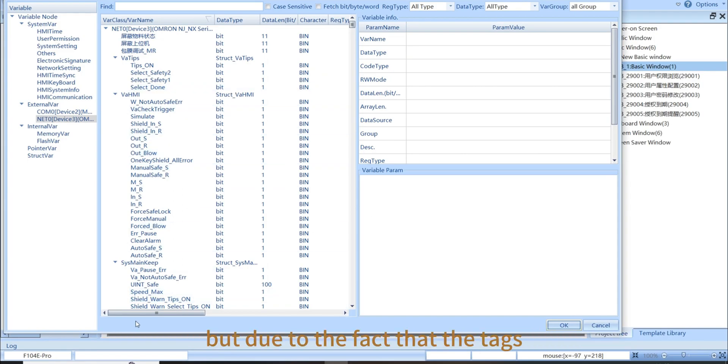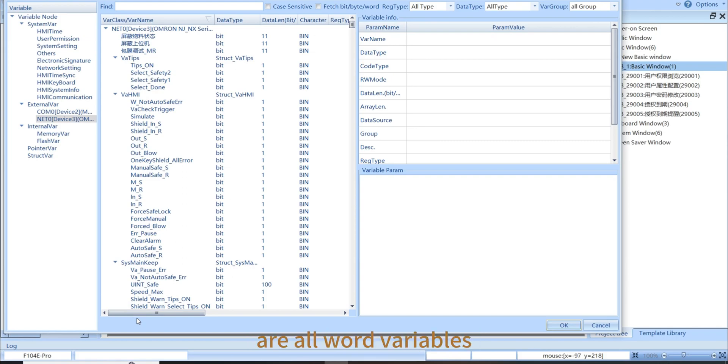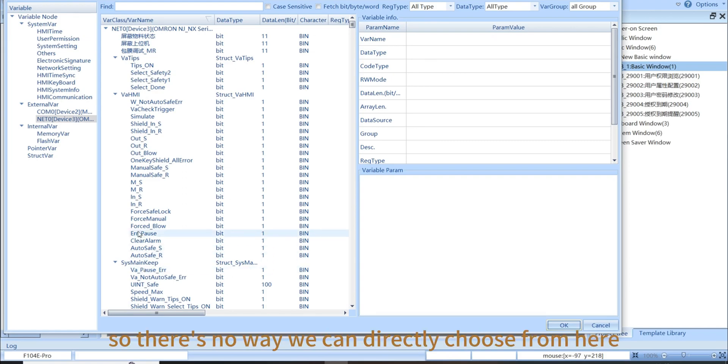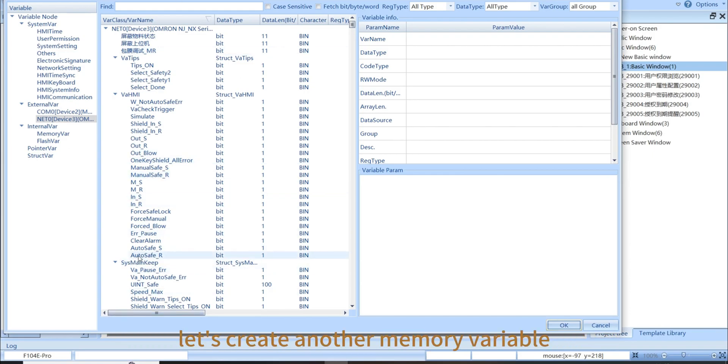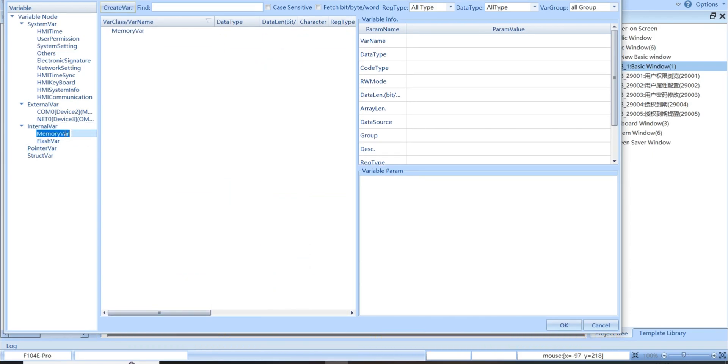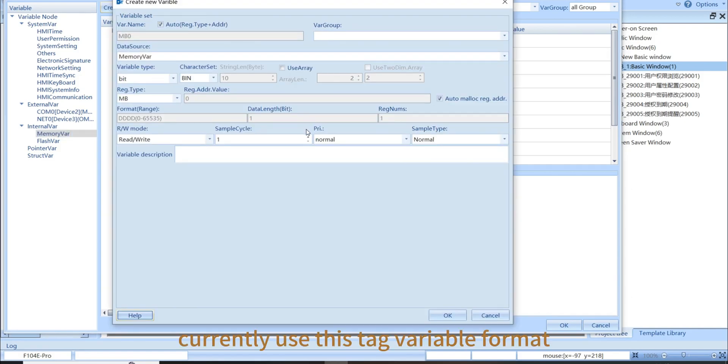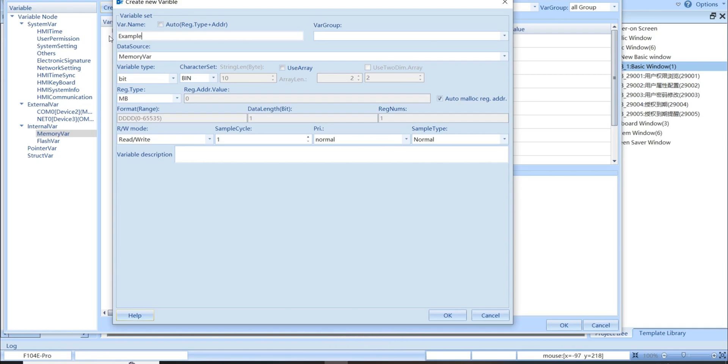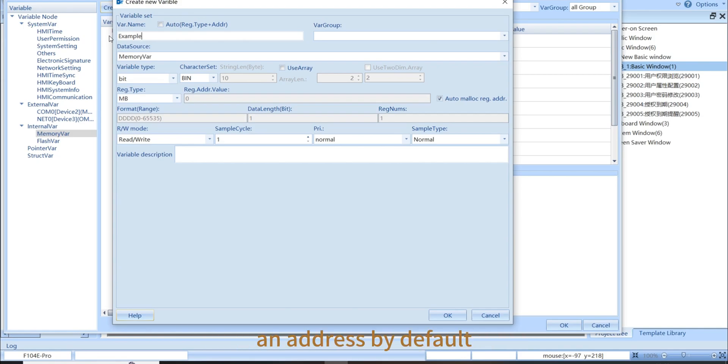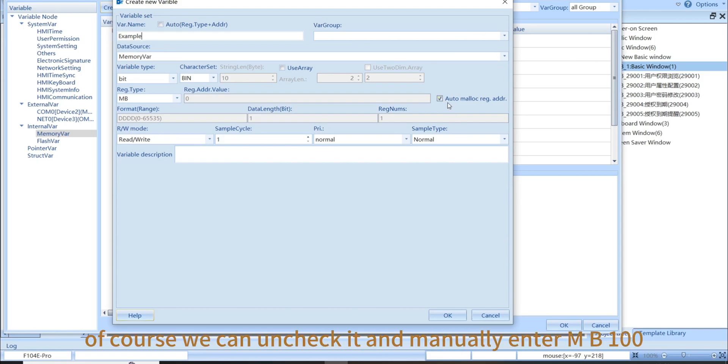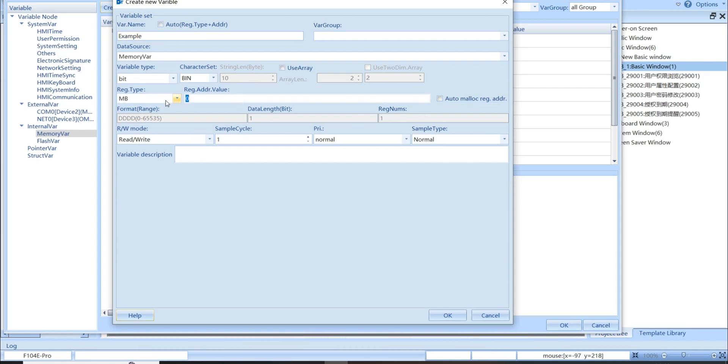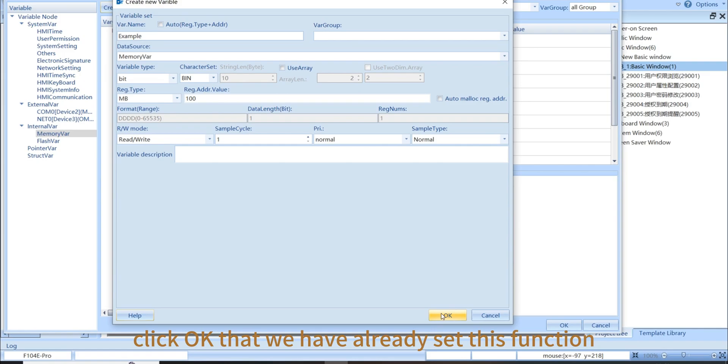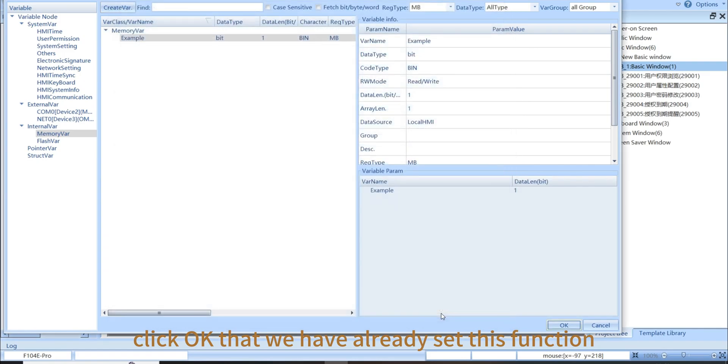But due to the fact that the tags we previously imported are all word variables, there is no way we can directly choose from here. Let's create another memory variable. Because the software currently uses this tag variable format, we can name it ourselves. Let's name it example bit variable. It is also automatically assigned an address by default. Of course, we can uncheck it and manually enter mb100 for it here. Click OK that we have already set this function.